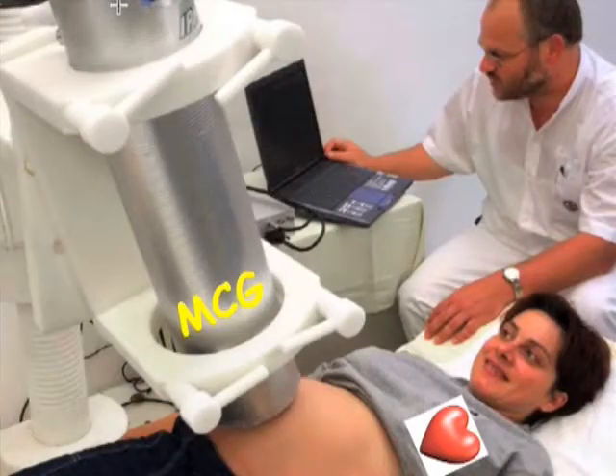And of course, you often also see a contribution from the mother's heart, but that is not difficult to remove, because you can always measure ECG simultaneously. Then you know when the heartbeat of the mother is — you have a trigger — so you can remove it.